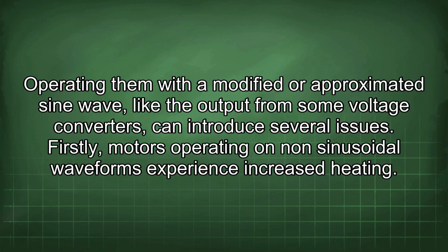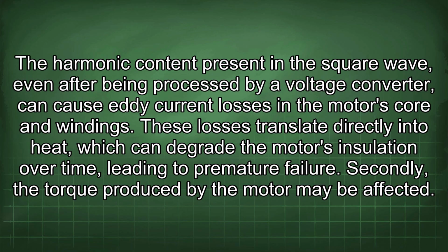Firstly, motors operating on non-sinusoidal waveforms experience increased heating. The harmonic content present in the square wave, even after being processed by a voltage converter, can cause eddy current losses in the motor's core and windings. These losses translate directly into heat, which can degrade the motor's insulation over time, leading to premature failure.